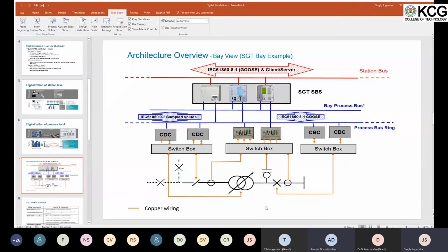That's a very wide area of loss, because there are different utilities. In India also you have a grid - 400 kV, 765 kV and 1200 kV grid - with very few losses in the grid itself. But once it goes to the distribution network, from 400 we step down to 275 or 220, then from 220 to 132 kV or 66 kV, and finally to what the consumer uses - either 415 volt or 230 volt, or for big industrial plants, 11 kV or 33 kV. So you can't compare losses like that directly, but overall losses will be less.